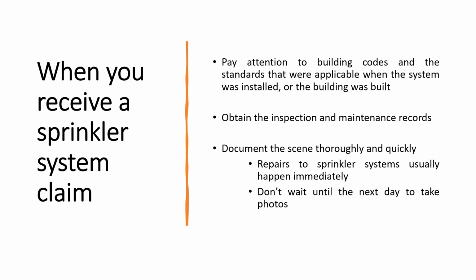Again, as I was saying before, when you receive a sprinkler system claim, try to pay attention to the building codes and the standards that were applicable when the system was installed or when the building was built. The codes do change, the standards have changed, and a system that looks today as if it wasn't properly installed may not be the case. It may have been installed at the time when it was approved, and it's still allowed to be working today. There are some exceptions, of course, but for the most part, we had to review in a little detail just to find out if it was still appropriate for the operation.